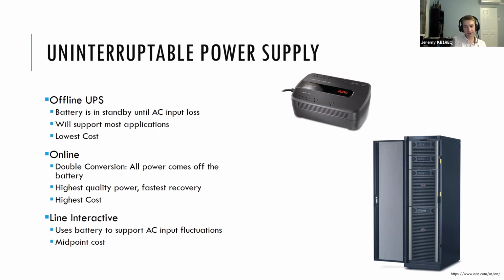For most devices, this is fine, because even though it's a relatively slow switch as far as a UPS is concerned, it's fast enough for most computer power supplies. There's enough capacitance in there that they're not going to see that hit. But in extremely critical environments, very sensitive electronics, obviously that wouldn't be acceptable, and that's where your other more complex power supplies come in.